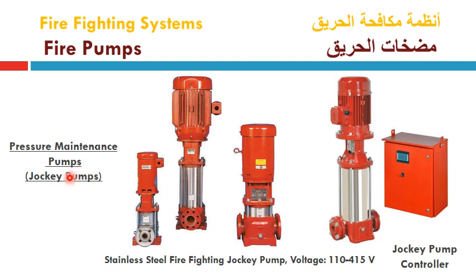The head of this pump should be slightly higher than the main fire pump head. For example, if the main fire pump head is 300 feet, then the jockey pump head can be 330 feet or 320 feet, about a 10% increase, or 20 or 30 feet higher than the main pump head, in feet or also in meters. The jockey pump has its own standalone controller.